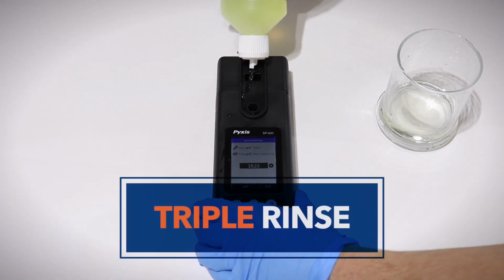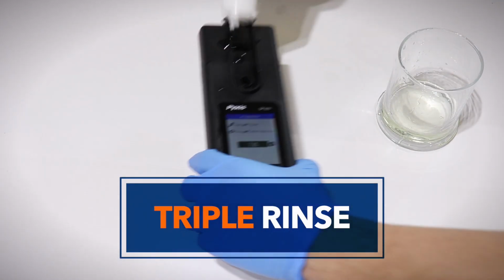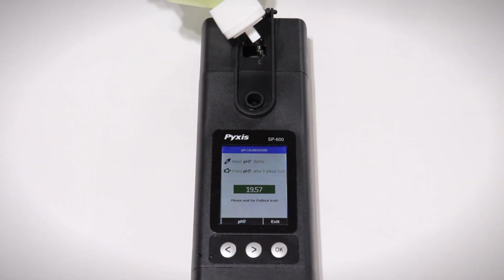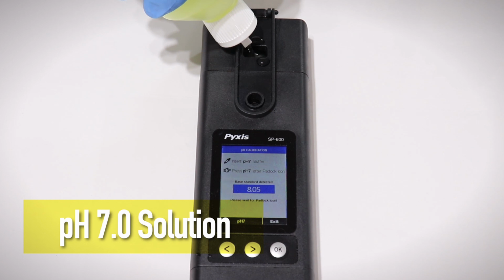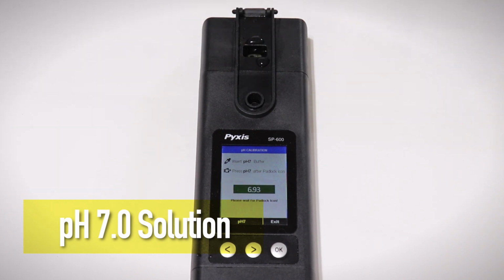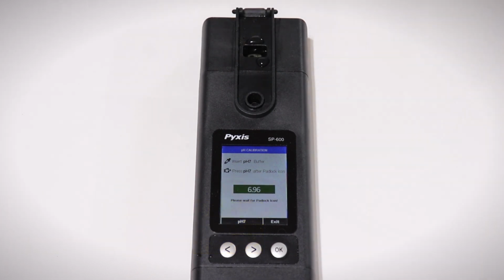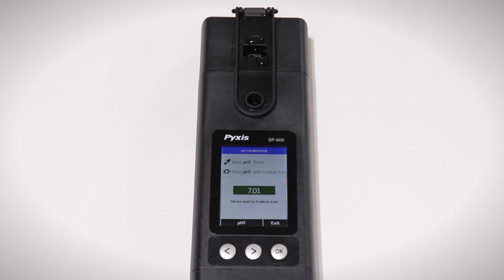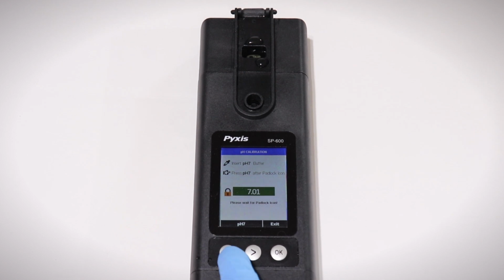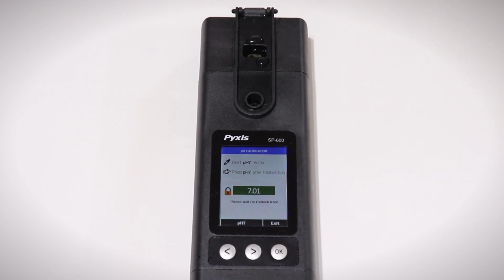Begin by triple rinsing the module with pH 7 calibration solution. Then fill the module with pH 7 calibration solution and wait for the lock icon to appear. Then press either of the arrow buttons to select pH 7. A success message will appear. Press either arrow button to select Next.